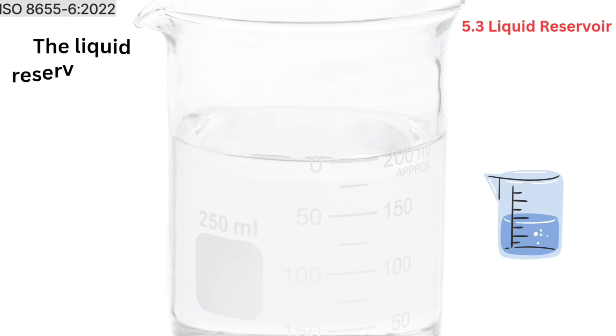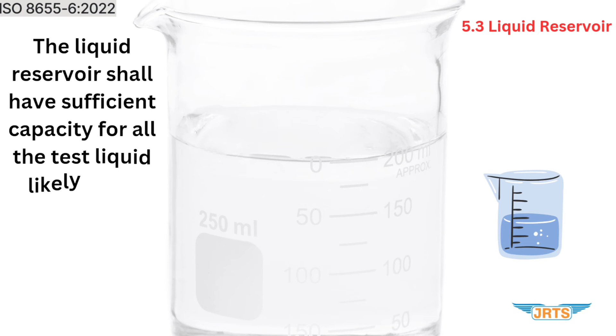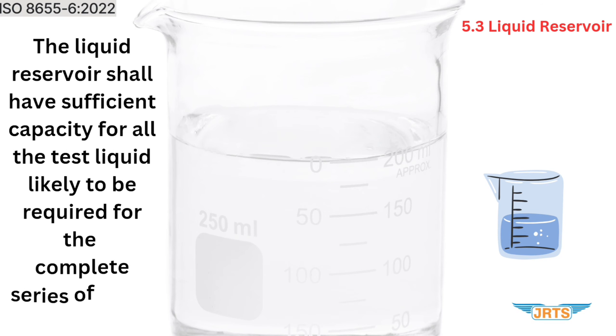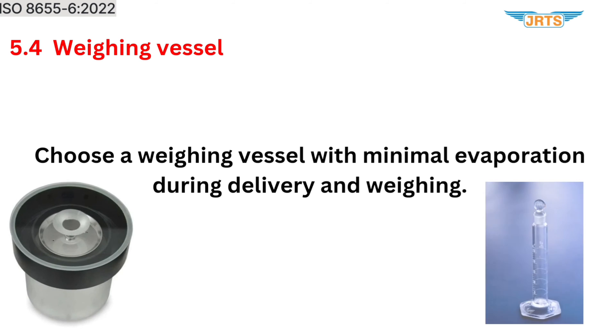Section 5.3, Liquid Reservoir: The liquid reservoir shall have sufficient capacity for all the test liquid likely to be required for the complete series of tests. Section 5.4, Weighing Vessel: Choose a weighing vessel with minimal evaporation during delivery and weighing. Section 5.5, Measuring Devices.